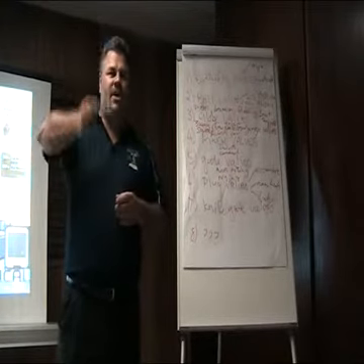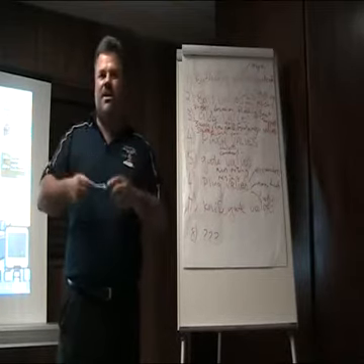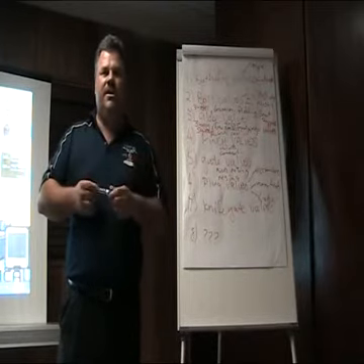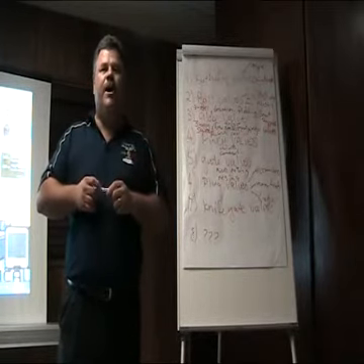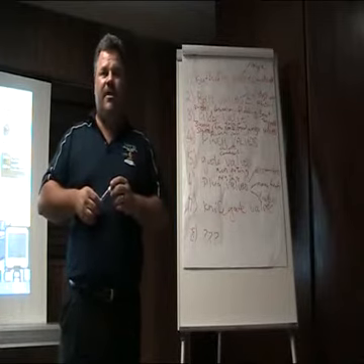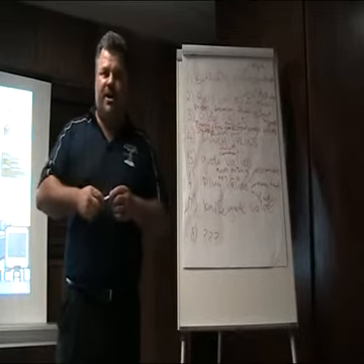So we're busy working with these guys, changing their terminology, changing their specs to say that these valves must be zero leakage, because isolation is zero leakage. That's the bottom line. They're putting in class 4, class 5, class 6 valves in there. It's leak rated valves for isolation purposes. But that was just for interest's sake.